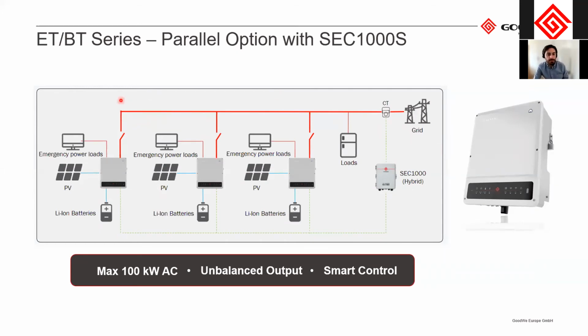This is a feature that's possible for the three-phase storage inverters. It's possible to connect them in parallel with a communication box. This is the SEC1000S for storage. With this one, you can connect up to 10 of the ET or BT inverters. The maximum capacity of an ET or BT inverter is 10 kilowatts. So with 10 of those, you could potentially have 100 kilowatt of storage inverters connected to a system. And this is the schematic of how it's connected.